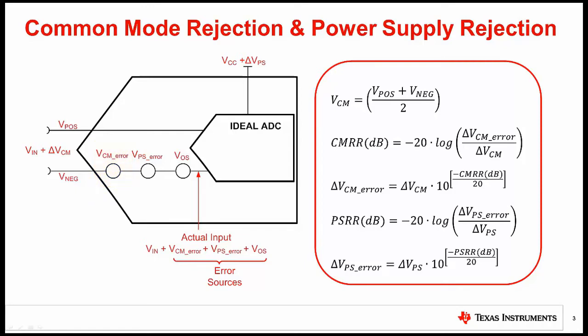The magnitude of this error source can be determined using the common mode rejection ratio, or CMRR, specification. CMRR is usually specified in decibels and can be calculated by taking negative 20 times the log of the change in common mode error divided by the change in common mode voltage. This equation can be rearranged to solve for the change in common mode error based on the change in common mode voltage.